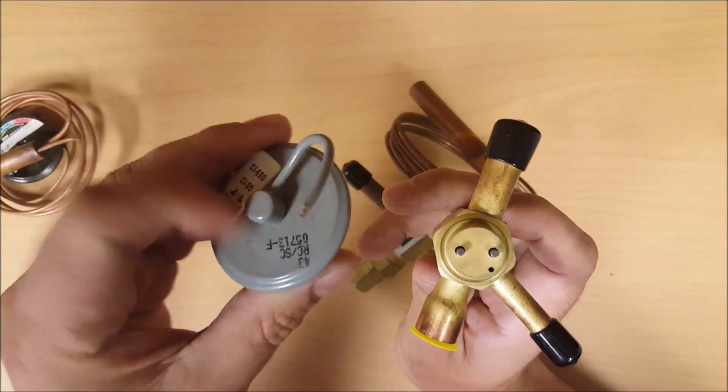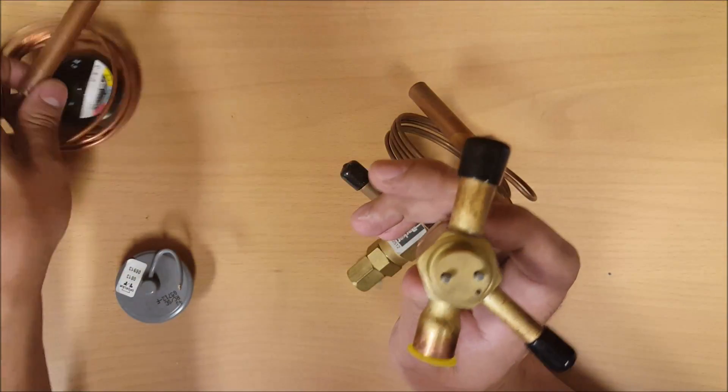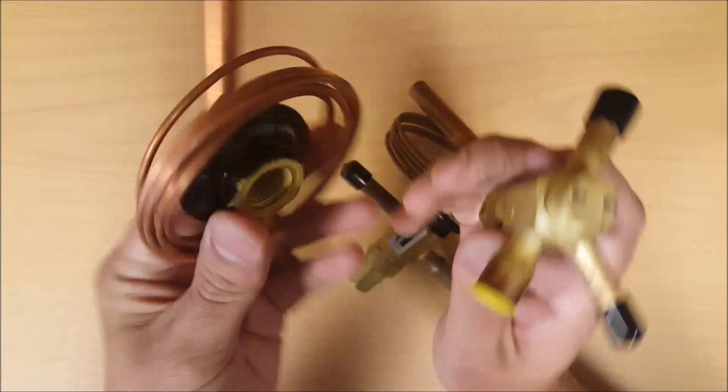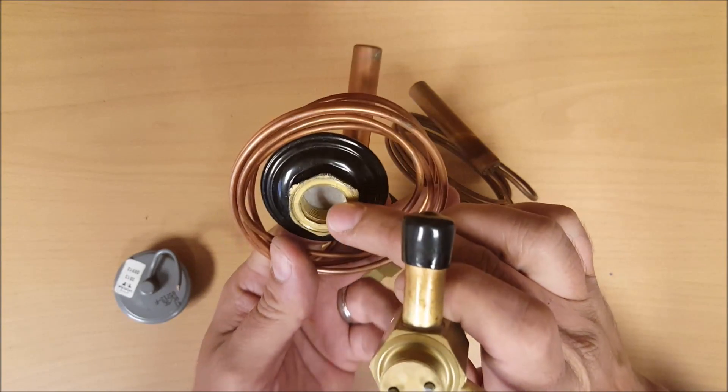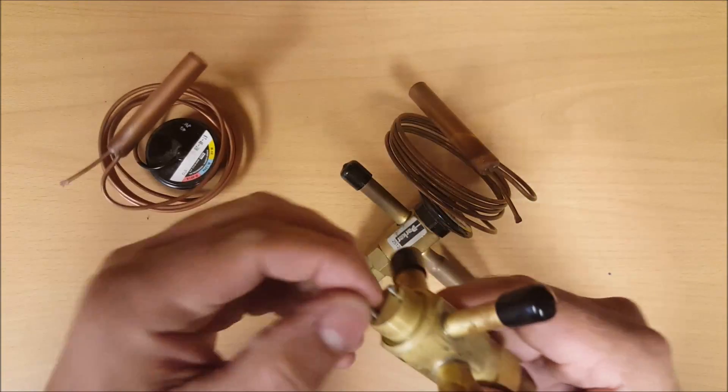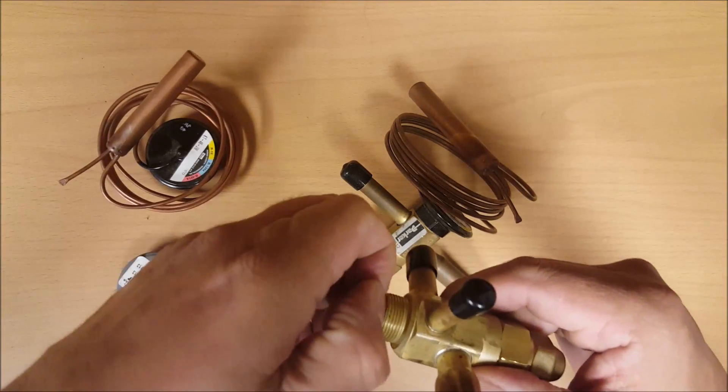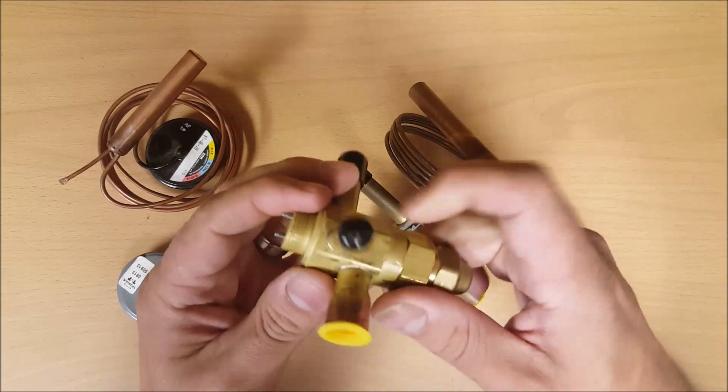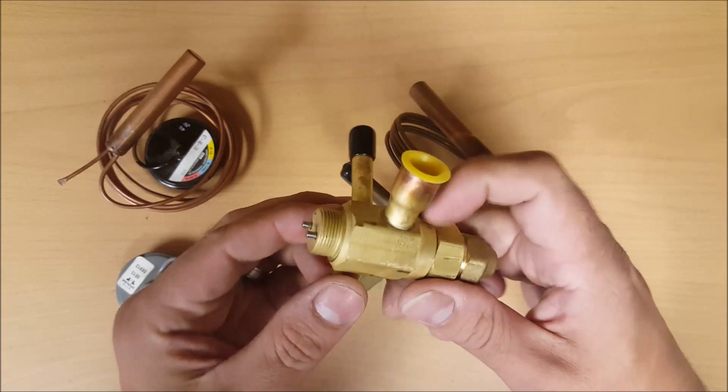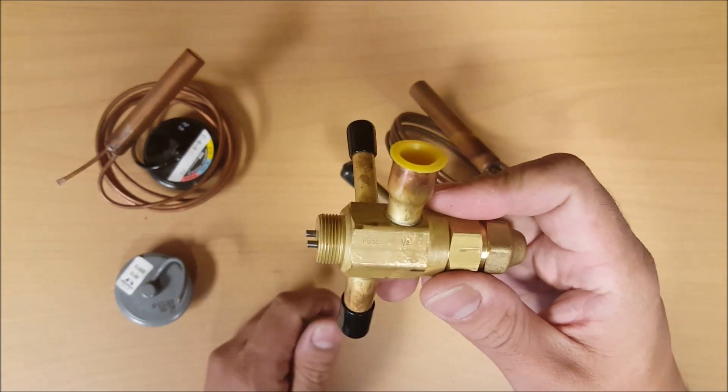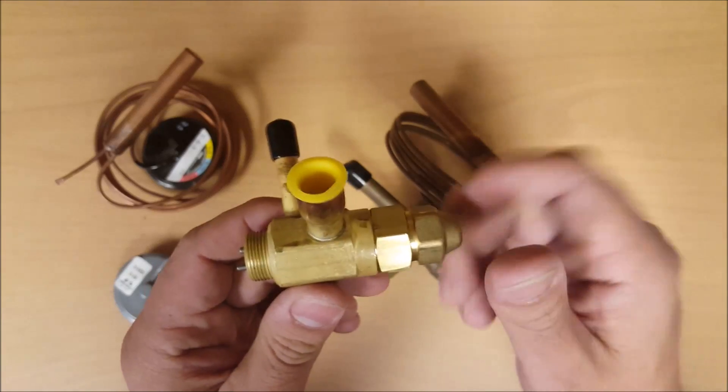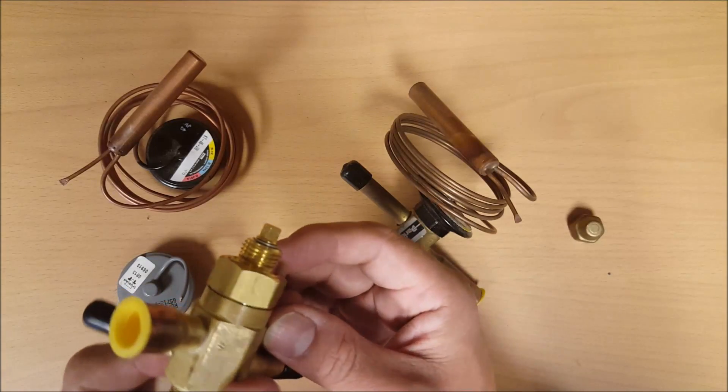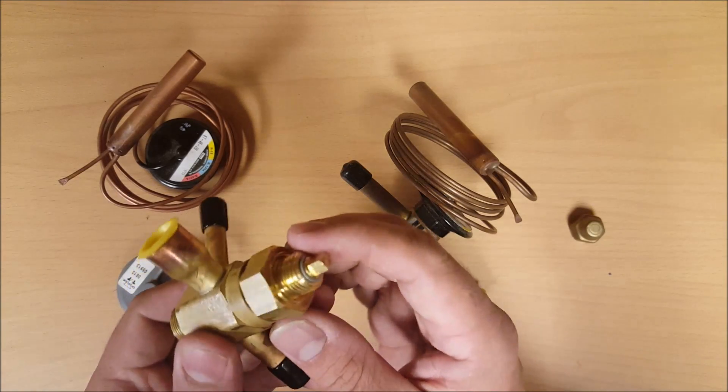This power element has the bulb that's reading temperature on your suction line. As the temperature fluctuates, it's going to move this disc in here up and down, putting pressure on these rods. That's going to either push or give way to your disc in here to allow more refrigerant or less refrigerant into your evaporator. That's in conjunction with a spring pressure here.